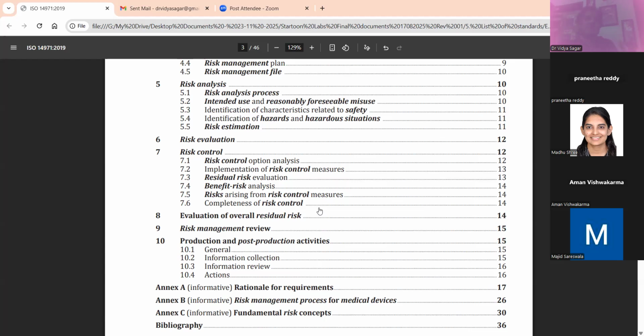So now you need to understand three things here. One is the environment, the hazardous situation. Hazardous situation is linked to usability engineering, or the human device interface. You have one document in usability engineering on how to use it and what the human device interfaces are, whether the human is the doctor or the patient, and the device. So it's more like a triangle. You have usability engineering, then risk management where you have residual risk, and these residual risks are directly proportional to or linked with your clinical adverse events.